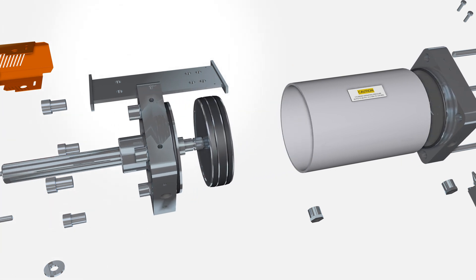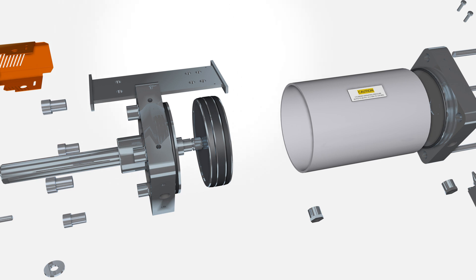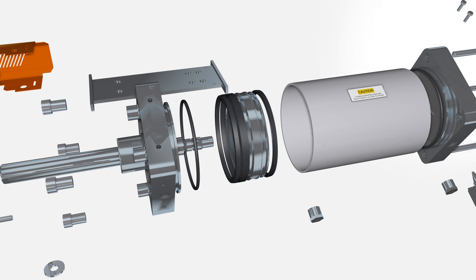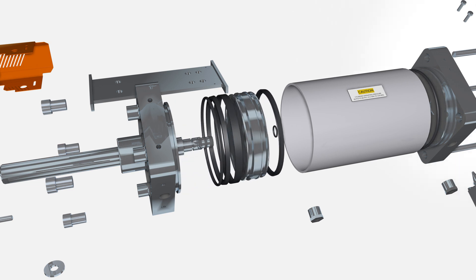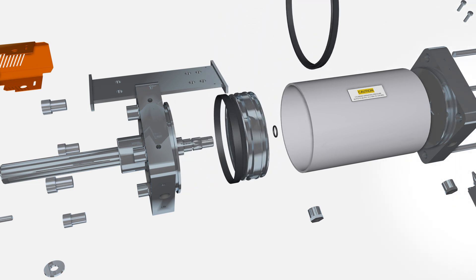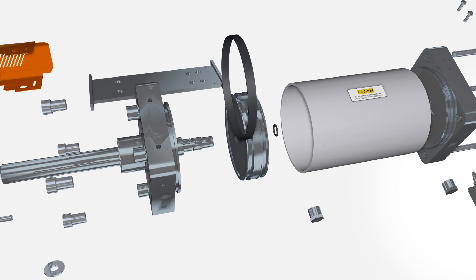Pull the end caps off the cylinder housing and remove the piston rod assembly from the housing. Completely disassemble the piston, discarding the o-rings, piston seals, wear sleeve and bushing.